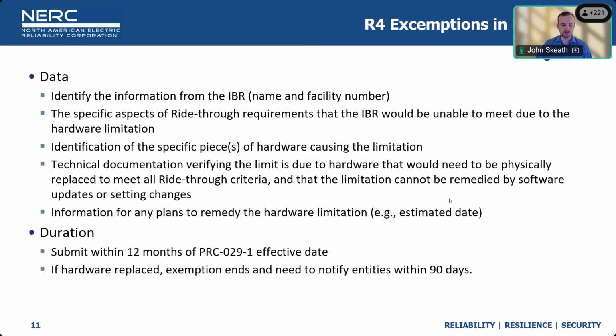And I'm going to delve deeper into the exemption process that's baked into PRC-29. We do require quite a significant portion of data in order to achieve an exemption. So we would need information about the IBR, so the name and facility number, the specific aspects of the ride-through requirements that are not able to be met, voltage or frequency, the specific pieces of hardware that are performing that limit, and technical documentation verifying that that limit is due to hardware that needs to be physically replaced to meet all the ride-through criteria, that the limitation cannot be remedied by software updates or setting changes, to really specify that, yes, this is a true hardware limit.